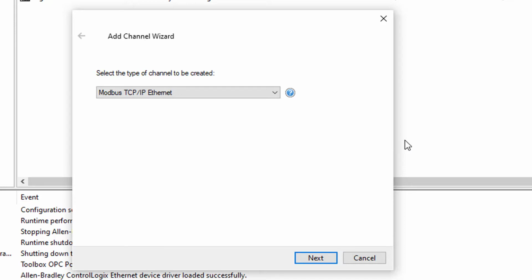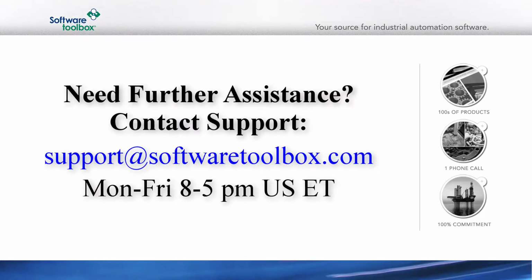At that point, you can either purchase and apply a license in the license utility for the unlicensed components, in our case the Modbus Suite, or if you prefer to keep using the unlicensed components in demo mode for the time being, the overall server runtime does have to be restarted to reset the 2-hour time period, which again will affect your licensed components. This video has shown the general steps required for quickly adding additional drivers and suites to an existing TOP Server installation when a full installation was not originally performed.